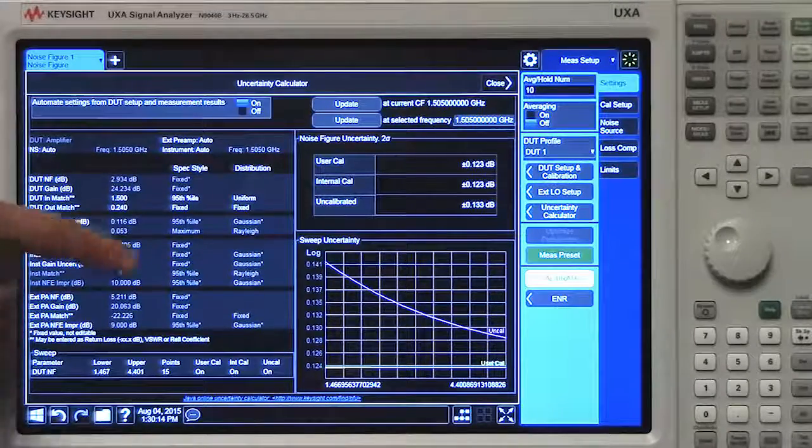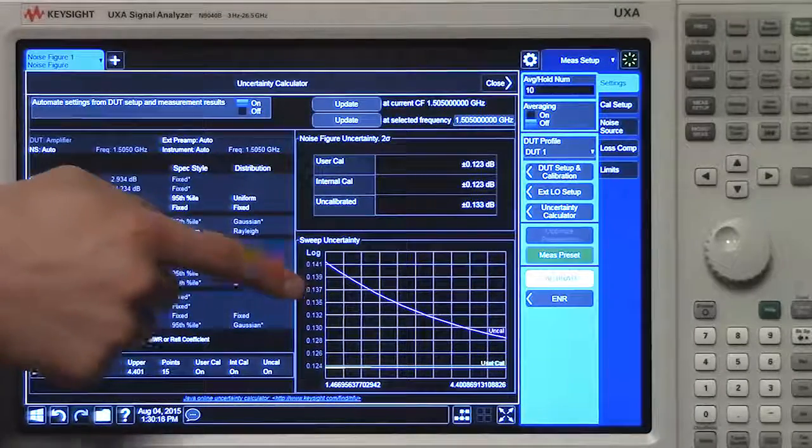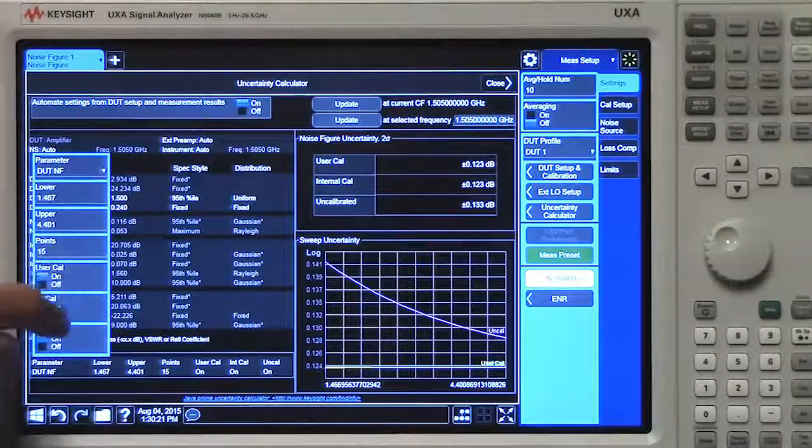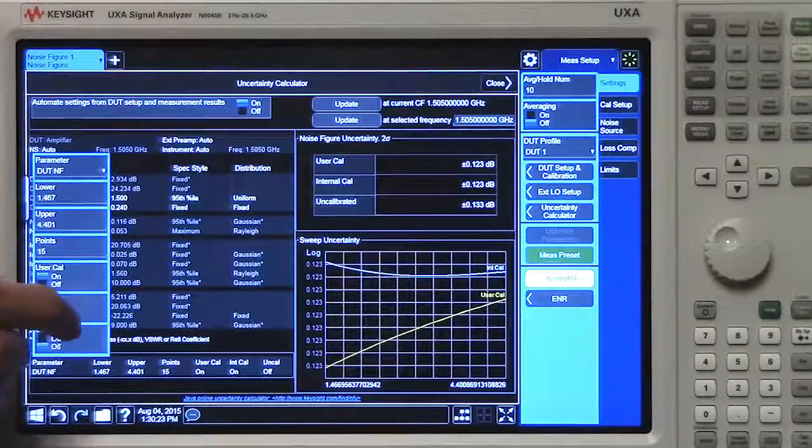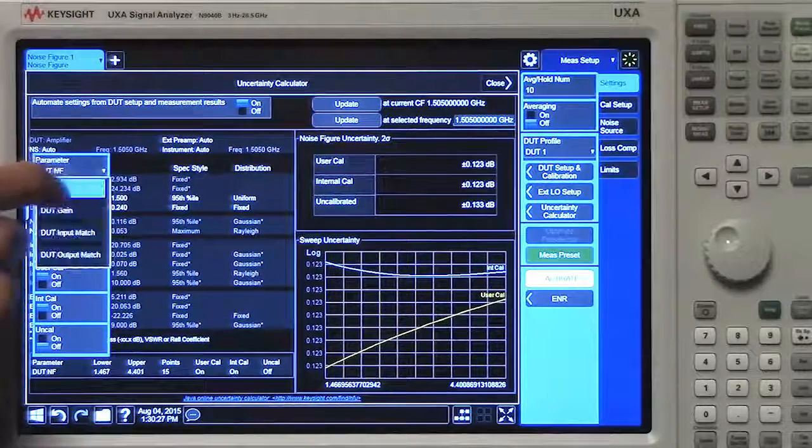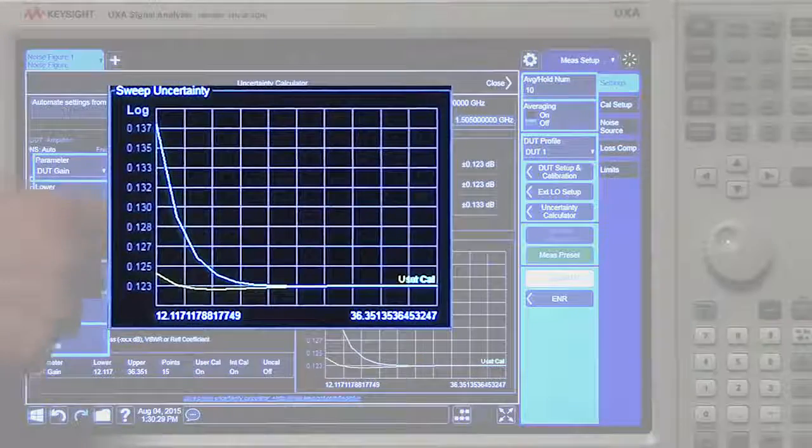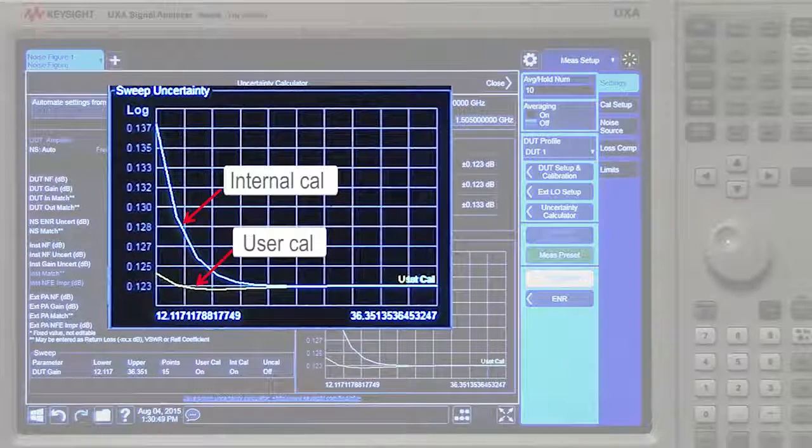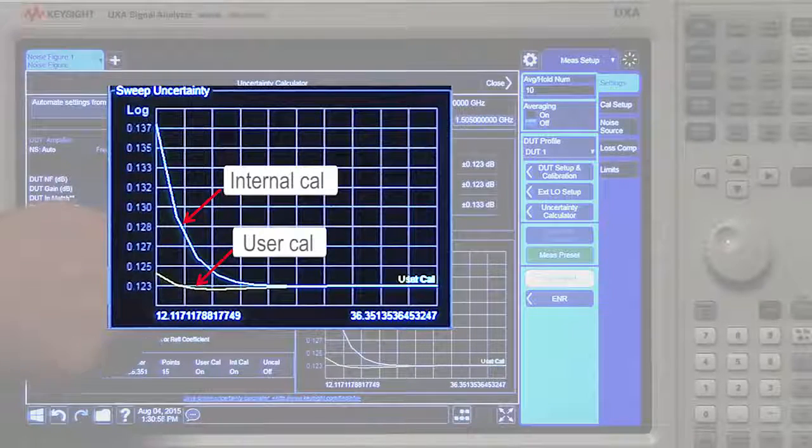You can also choose to sweep any number of parameters. I'm going to turn off the uncal trace, and I'm going to sweep the gain. And you can see the difference between the user cal and the internal cal. The internal cal suffers a little bit for lower gains, so in the situation of a DUT that has a low gain, you'd probably prefer to do a full user calibration.